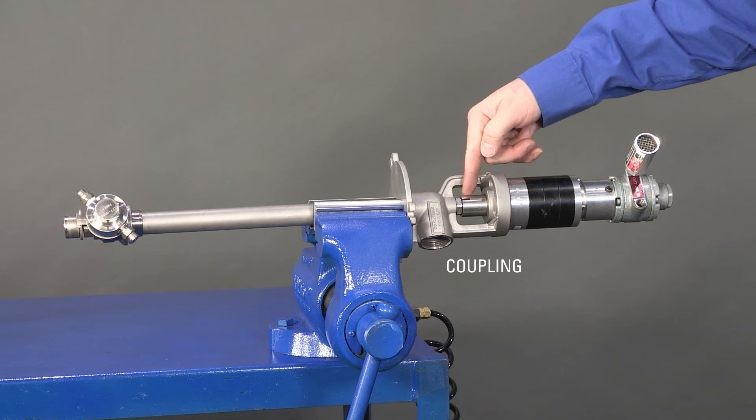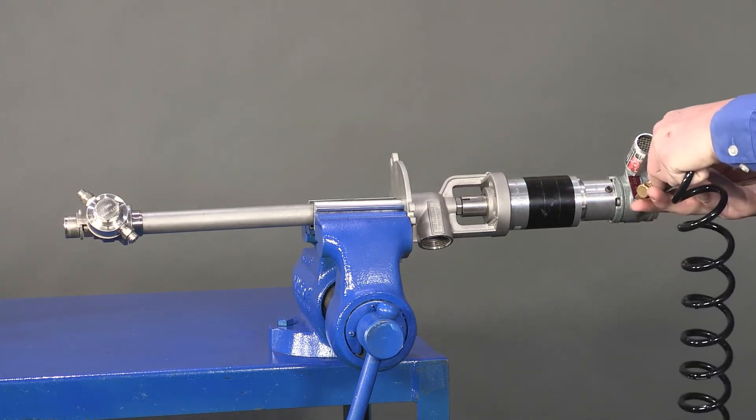Inspect the coupling between the gearbox and the inlet body. While supplying compressed air to the motor, check the coupler for rotation.